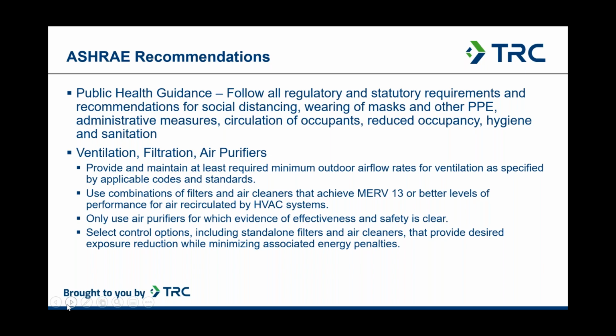ASHRAE's primary recommendations include, one, confirming that the building HVAC systems are providing a minimum outdoor air introduction rate; two, supplementing those systems with a minimum MERV 13 filtration system, especially in recirculated air; and three, the supplemental use of standalone air purifiers with proven effectiveness and safety.